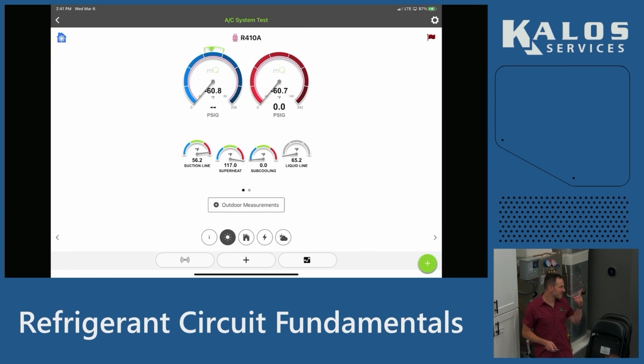High superheat means we don't have an airflow problem, so just check that off the list. If you were watching earlier when I first started to do it, I started to get that number up and then it started to come back down, because the TXV tries to maintain a constant superheat. The metering device actually adjusted for the flow that I gave it to maintain that constant superheat. So let's answer that question.